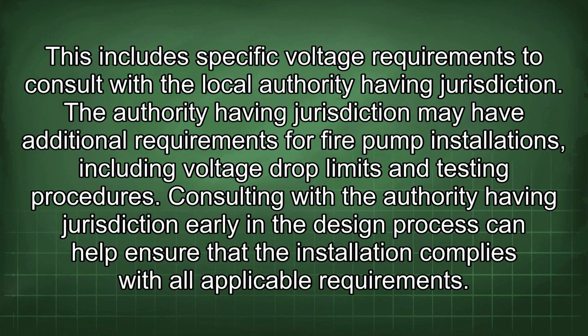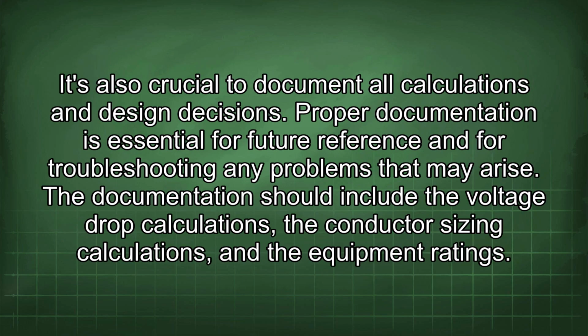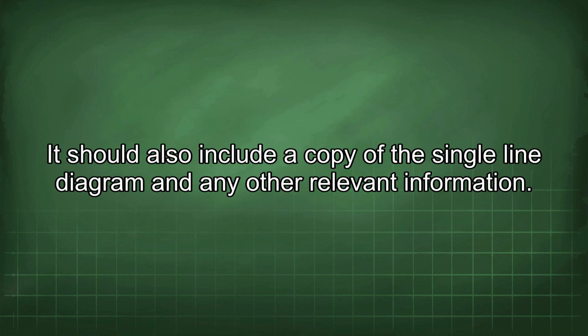This includes specific voltage requirements to consult with the local authority having jurisdiction. The authority having jurisdiction may have additional requirements for fire pump installations, including voltage drop limits and testing procedures. Consulting with the authority having jurisdiction early in the design process can help ensure that the installation complies with all applicable requirements. It's also crucial to document all calculations and design decisions. Proper documentation is essential for future reference and for troubleshooting any problems that may arise. The documentation should include the voltage drop calculations, the conductor sizing calculations, and the equipment ratings. It should also include a copy of the single line diagram and any other relevant information.